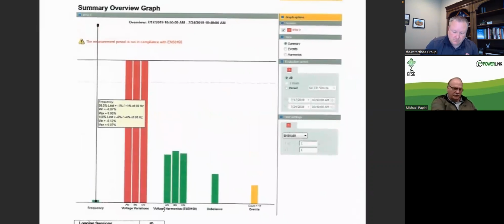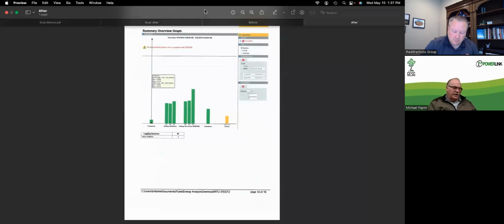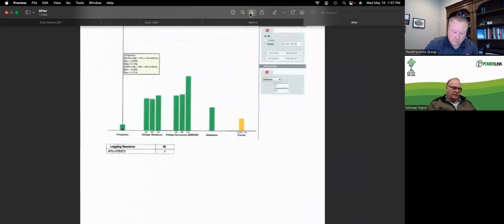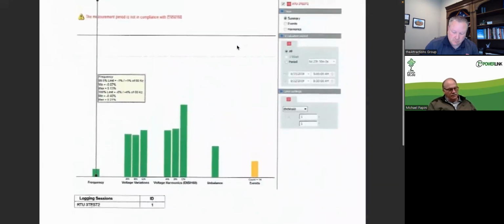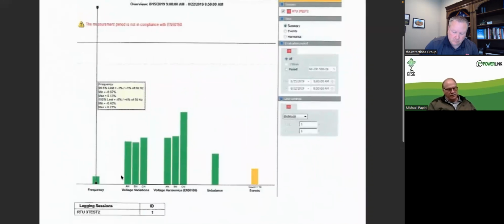After we put our box on, go here. You can see that, and this is all on the same motor. We just data logged it, and there's the reduction in harmonic heat. So now we're back in the green on everything. The motor's happy, saving 10 kW, and that's just on one motor.